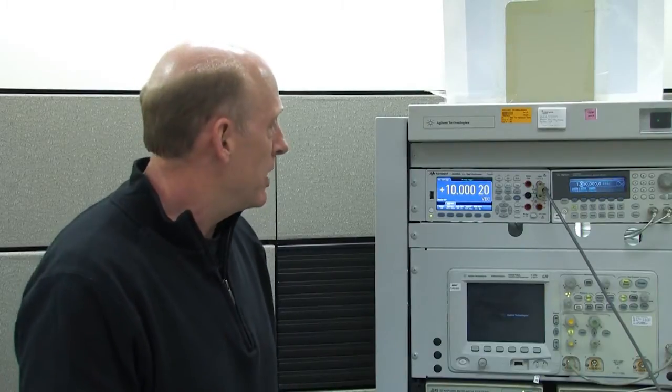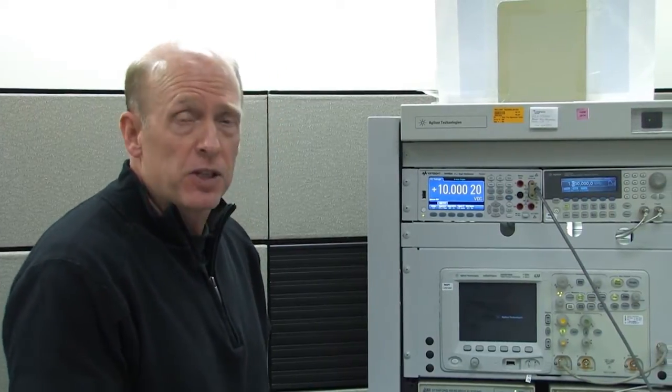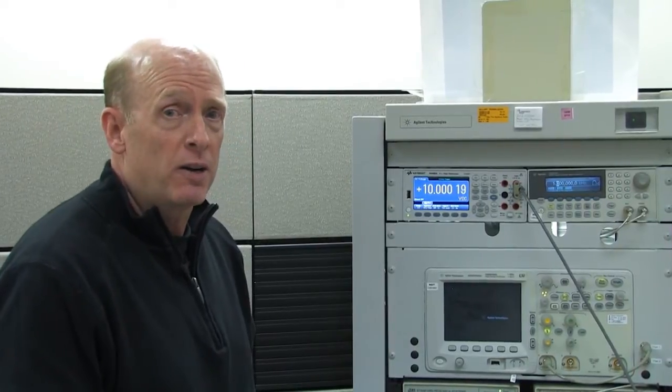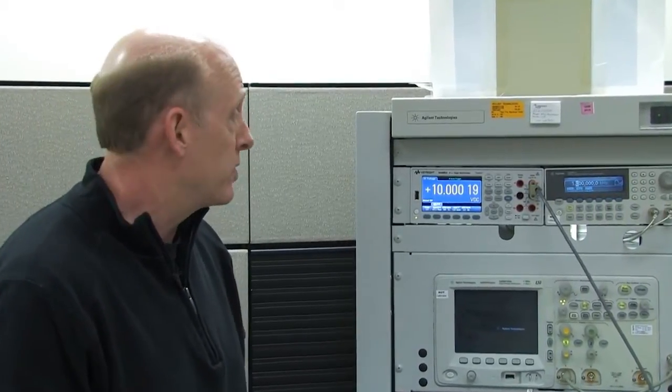We have installed the 34465A multimeter in the system rack and have allowed it to thermally stabilize. As you can see, given the same 10 volt source, we are seeing a reading difference of several counts.